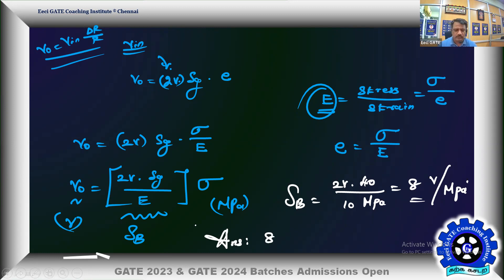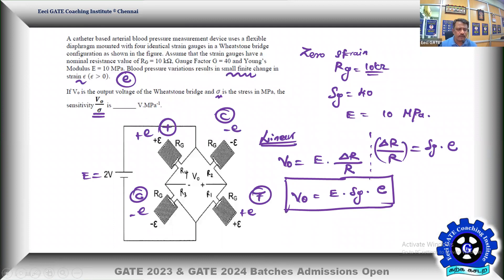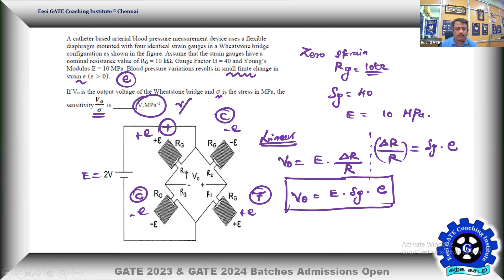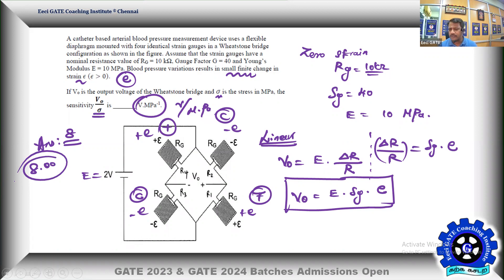The answer is 8 V/MPa. The unit is volts per mega-pascal as required. If decimal places are specified, it would be 8.00. This is an interesting problem exploiting the basics of strain gauges in a full passive bridge, which performs perfectly linear transduction.